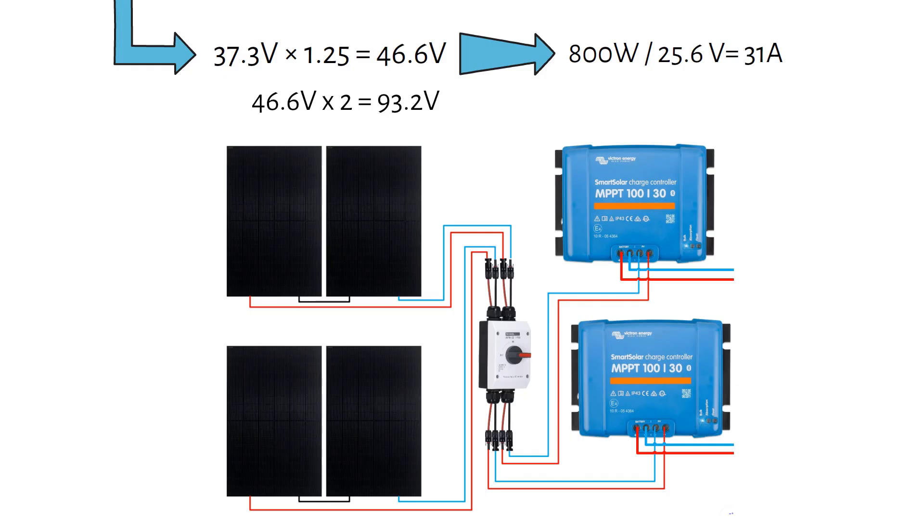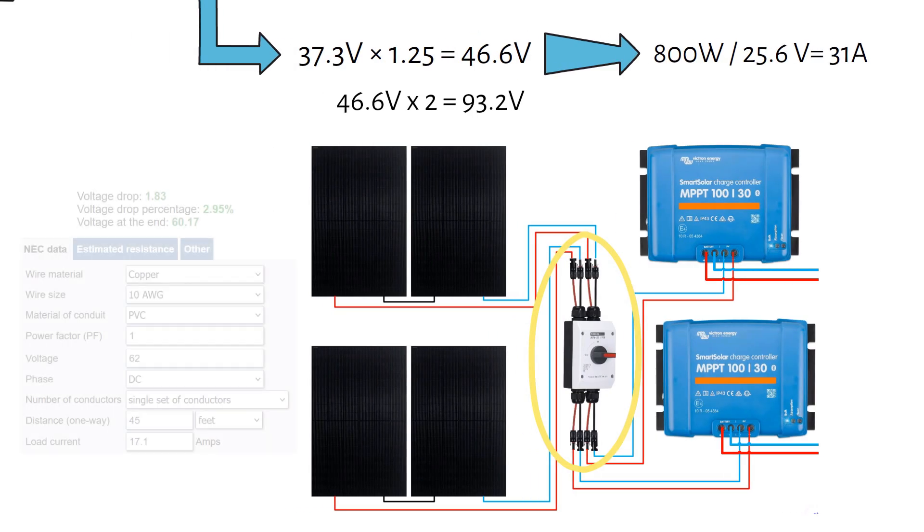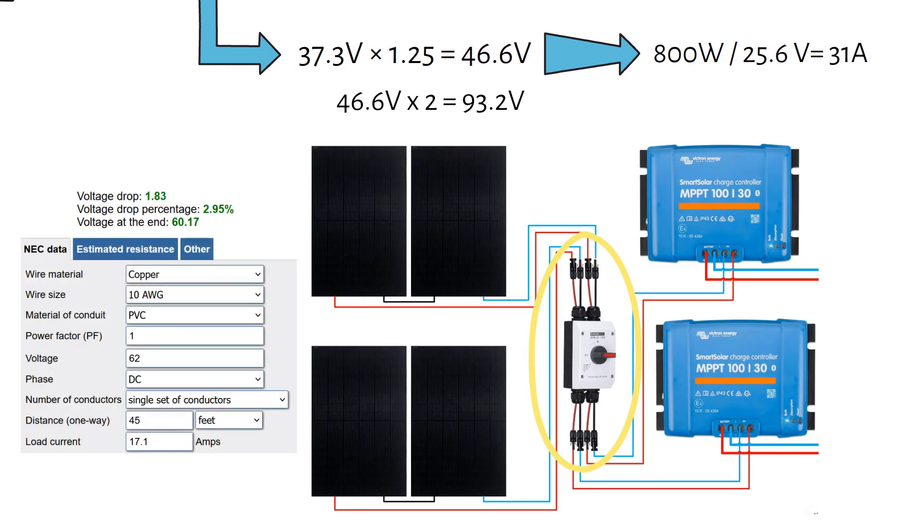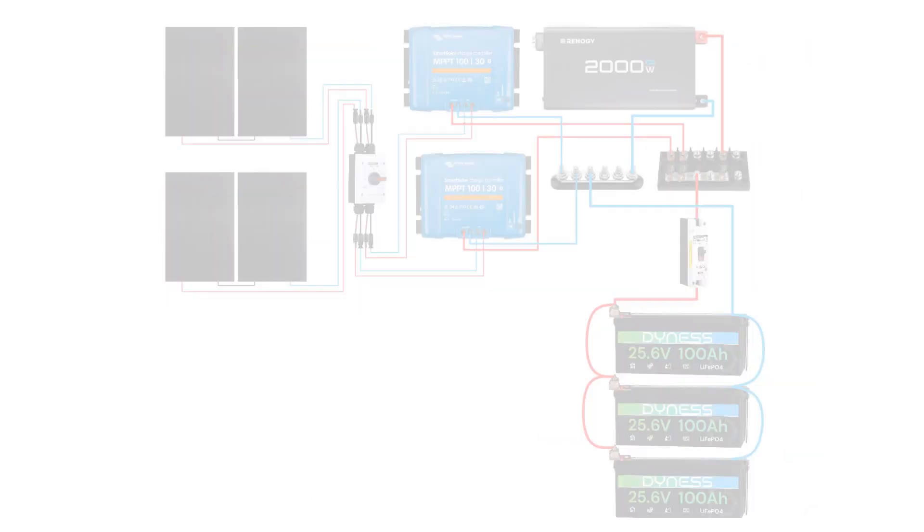I connect the panels through a solar disconnect switch. The cable run from the panels to the charge controller is about 45 feet or 14 meters. I use 10 gauge or 6mm square PV wire to keep the voltage drop under 3%.